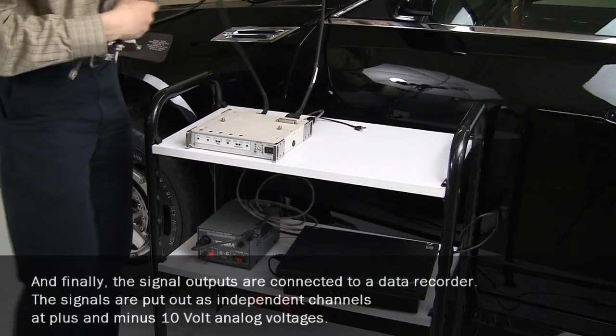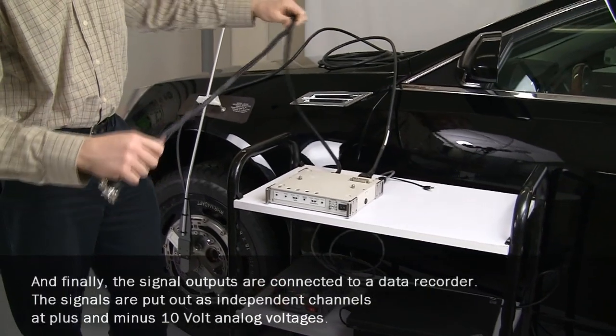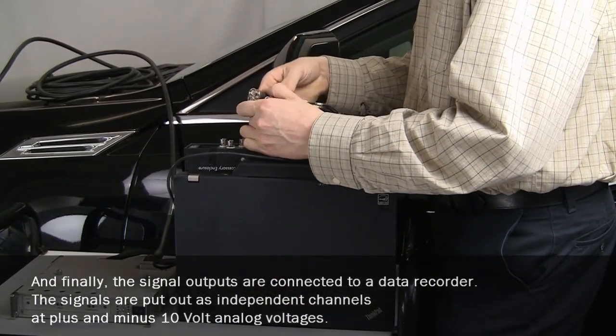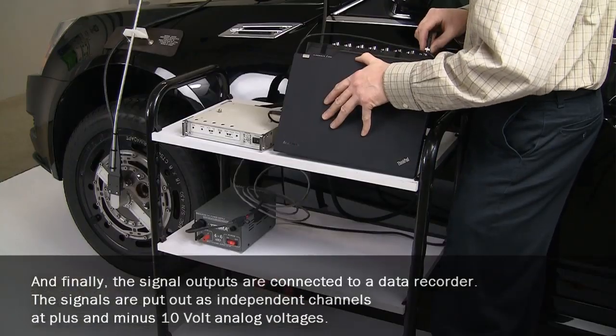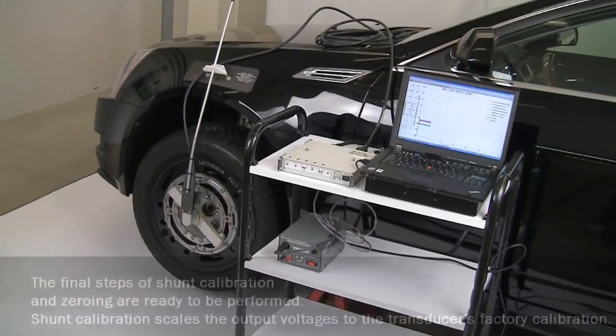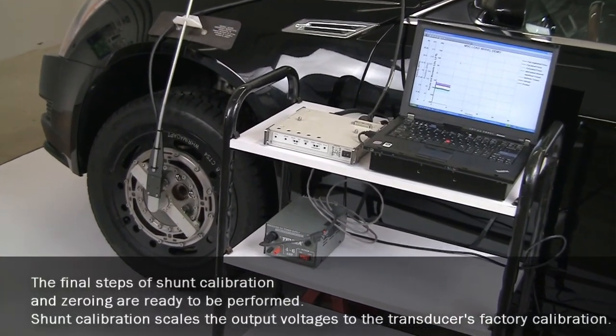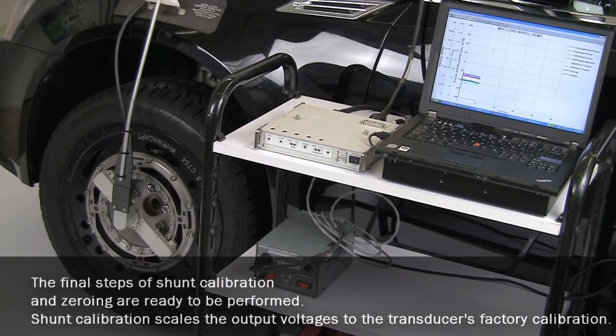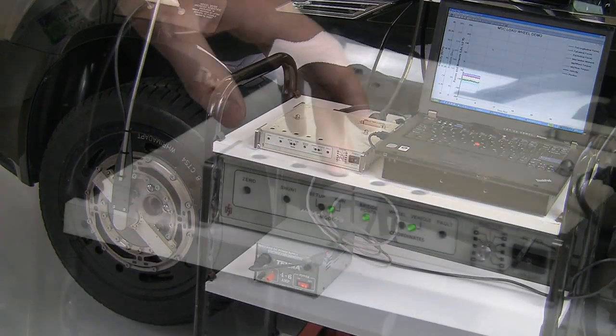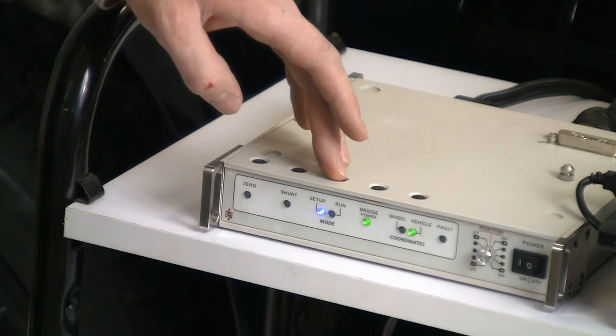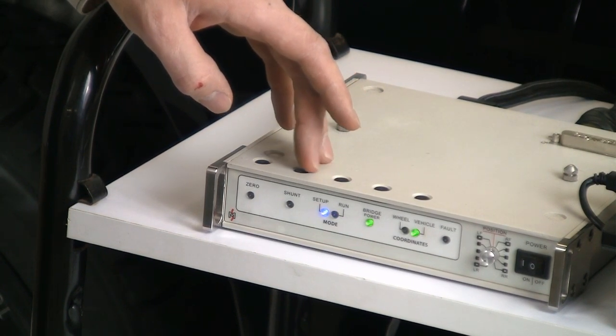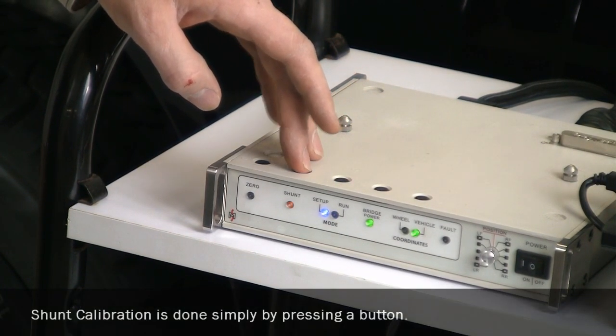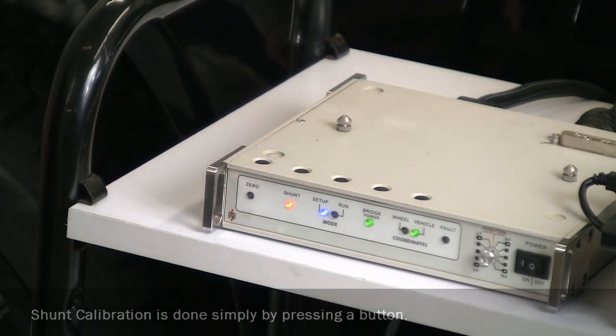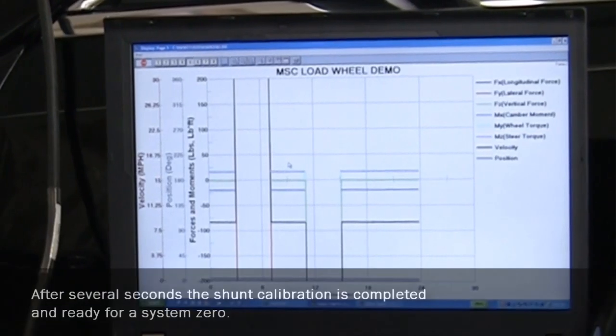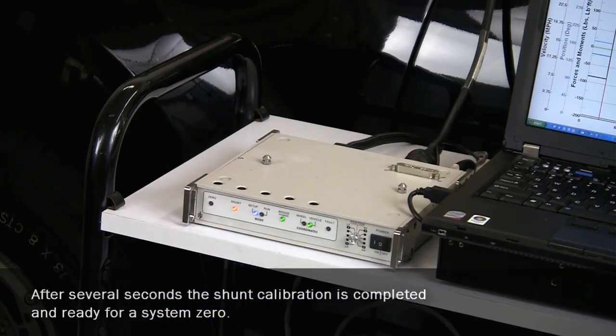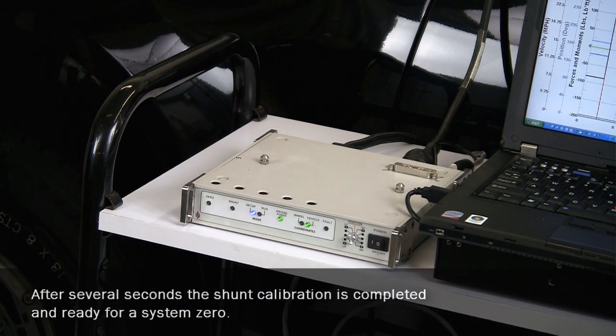And finally, the signal outputs are connected to a data recorder. The signals are put out as independent channels at plus and minus 10 volts analog voltages. The final steps of shunt calibration and zeroing are ready to be performed. Shunt calibration scales the output voltages to the transducer's factory calibration. Shunt calibration is done simply by pressing a button. After several seconds, the shunt calibration is completed and ready for a system zero.